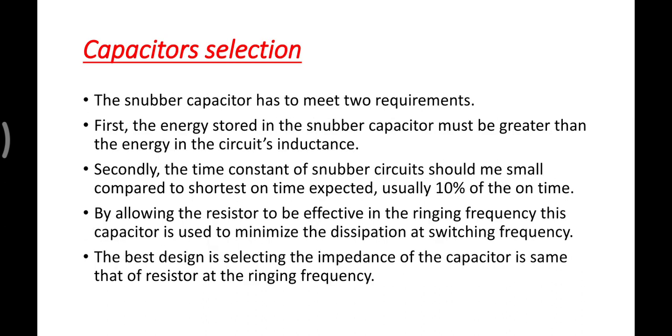So if you want to select the capacitor, it must satisfy two basic requirements. What are those basic requirements? First, the energy stored in the capacitor must be greater than the energy in the circuit inductance. And second, the time constant of the snubber circuit should be small. So these are the two important points we have to consider while selecting the capacitor.